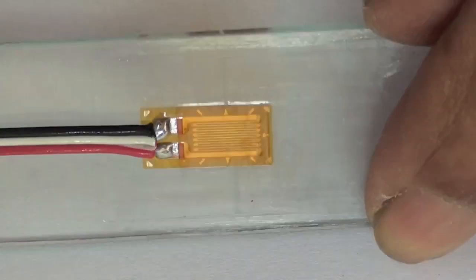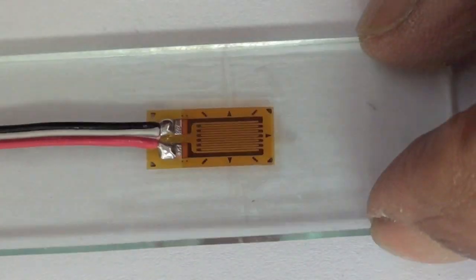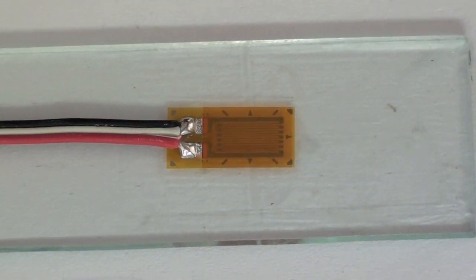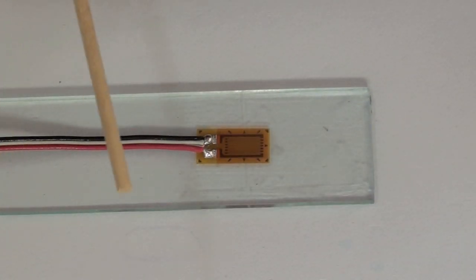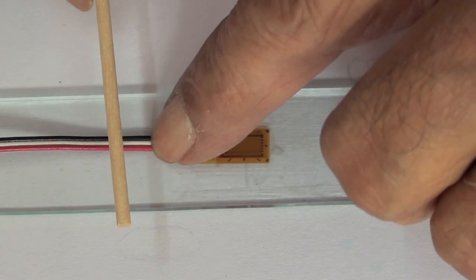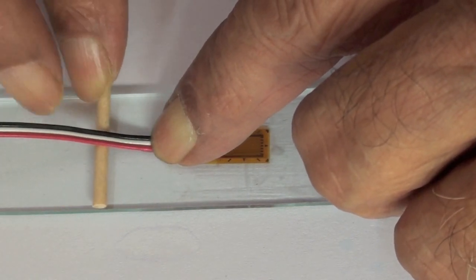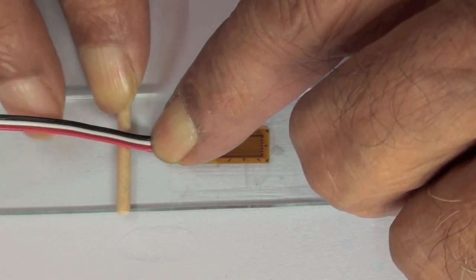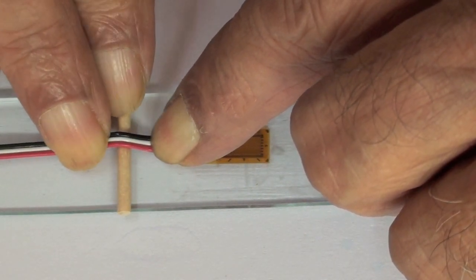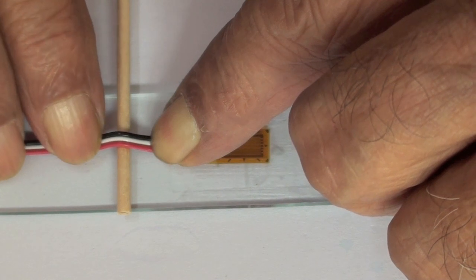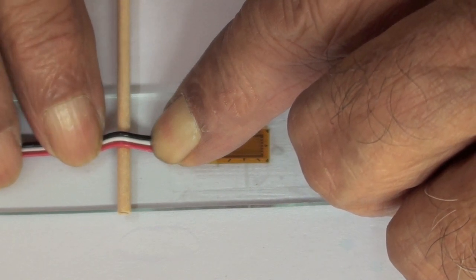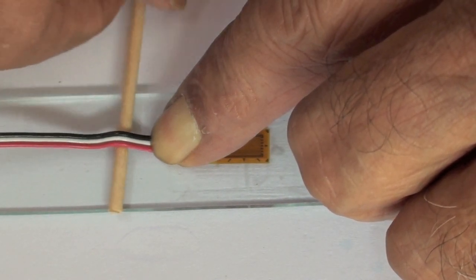In all strain gauge installations, it is very desirable to have some flexibility in the lead wires to minimize the possibility of breaking of the solder joints due to differential movement between the beam and the wire during testing. This is done by clamping the lead wire near the solder joints, then pressing a small round object under the wire and pressing the wire down on the other side to create a strain relief loop in the wire.